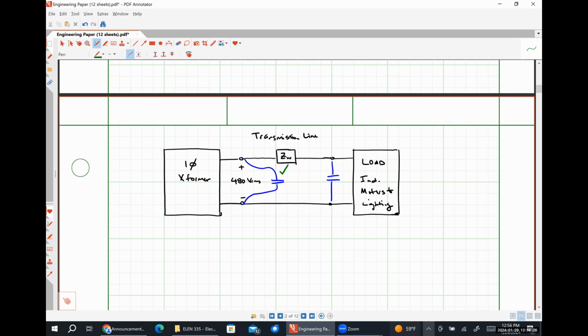And B, the loads can change, right? Meaning you might restructure your plant, this, that, and the other. Having to redo all of that every time you make some change would be a total pain. Whereas putting a capacitor bank on the transformer side is effectively static throughout the lifetime of your facility.